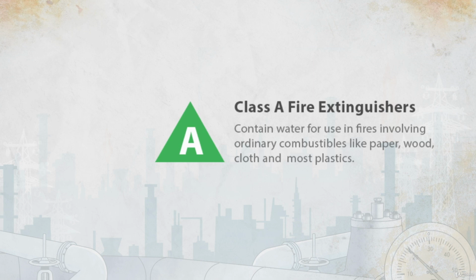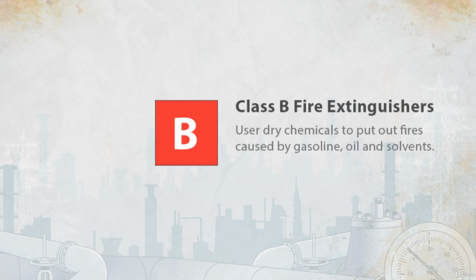The numerical rating listed on Class A extinguishers represents the amount of water they can hold and the amount of fire it is capable of extinguishing. Their geometric symbol is a green triangle. Class B extinguishers are for the flammable or combustible liquids, such as gasoline, kerosene, grease, and oil. The numerical rating for Class B extinguishers represents the approximate number of square feet of fire they are capable of extinguishing. Their geometric symbol is a red square.